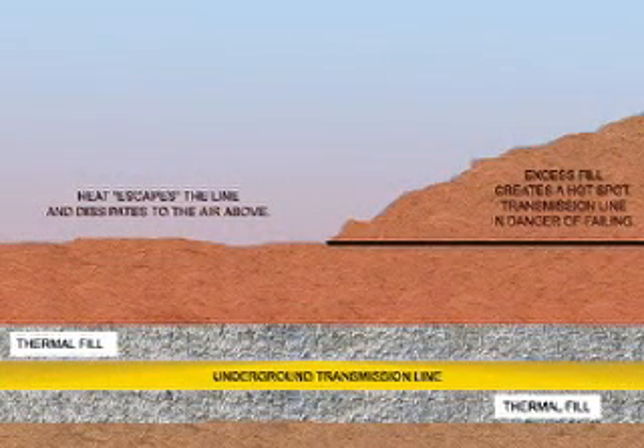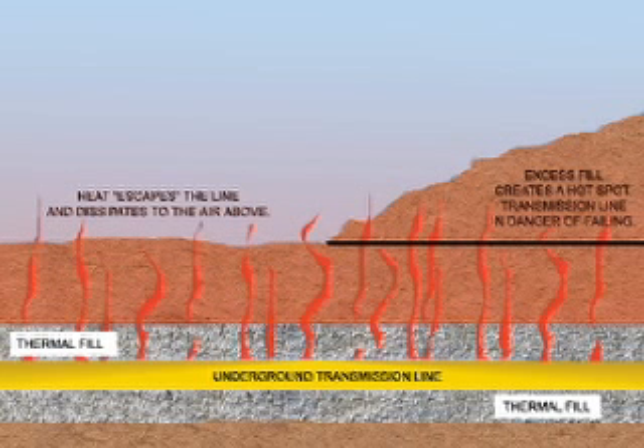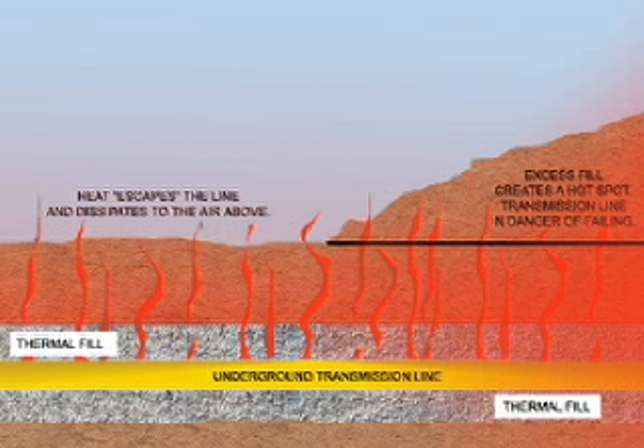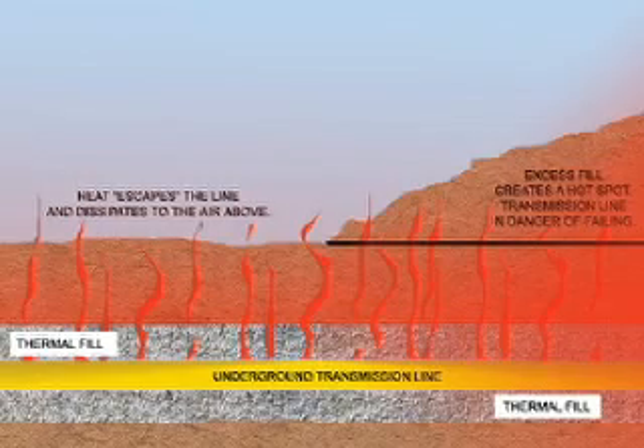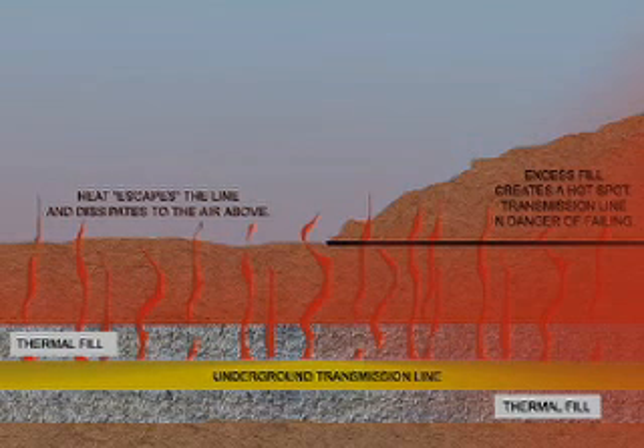If the grade over the underground transmission line is changed, the ability to dissipate heat could be compromised. Additional fill can cause excessive heat buildup and affect the capacity of the circuit. This also can create a hot spot, which can cause damage over time. If the grade is cut, the circuit will be vulnerable to future damage. Any plans that include grade changes over ATC underground transmission lines must be reviewed and approved prior to construction.